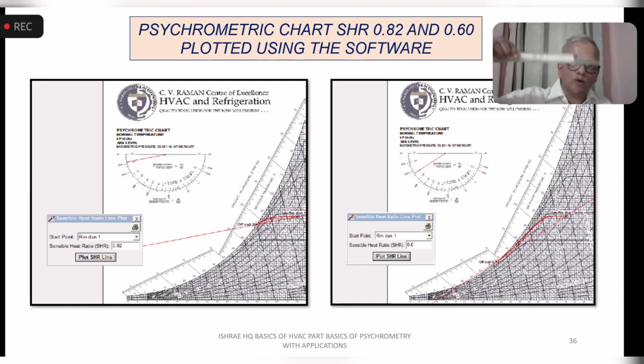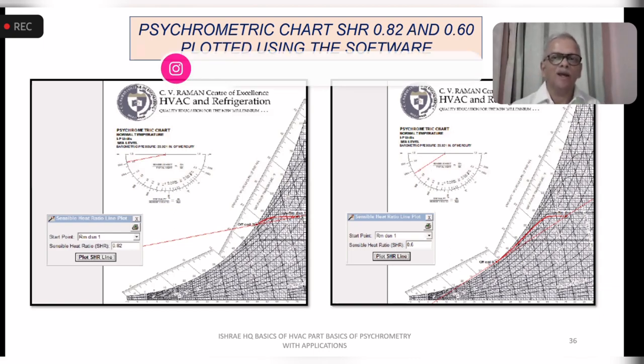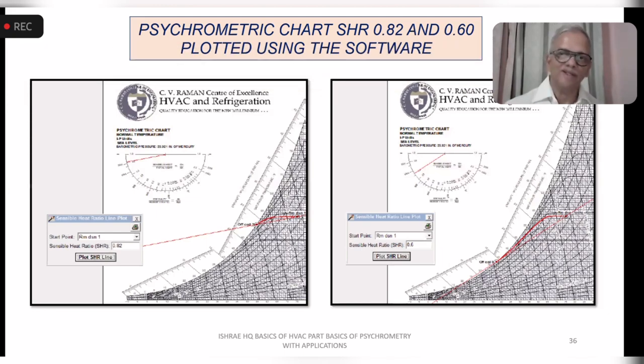This is the slide rule or the sliding scale. So you use this edge parallel on this line. You put that matching on this line and just move the roller and move this scale on the psychrometric chart and then pass through this point, which will draw that line exactly parallel to this. Otherwise, you'll have to use a set of set squares and keep moving. And in that process, there is a likelihood that it will slip and the angle will change, which means the sensible heat factor, which is required, will not be the same when you reach here.